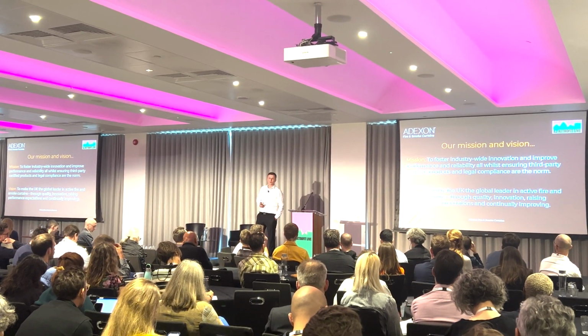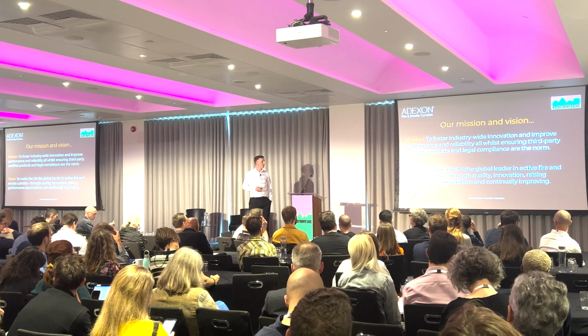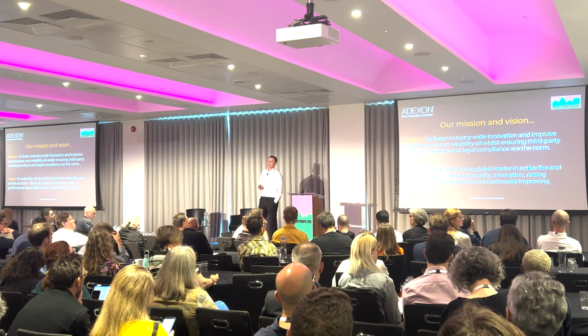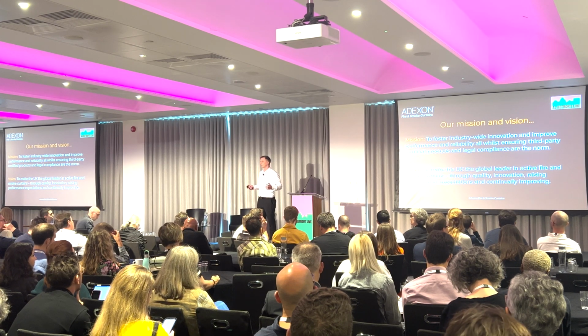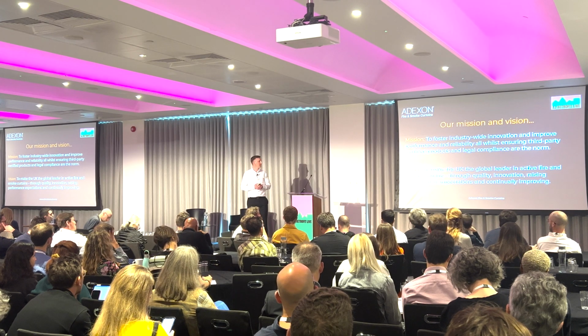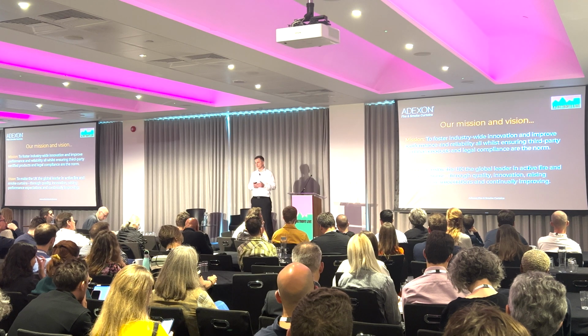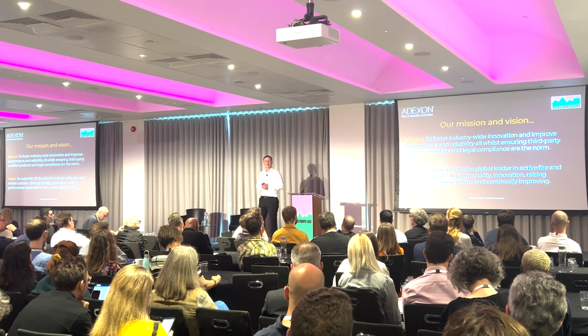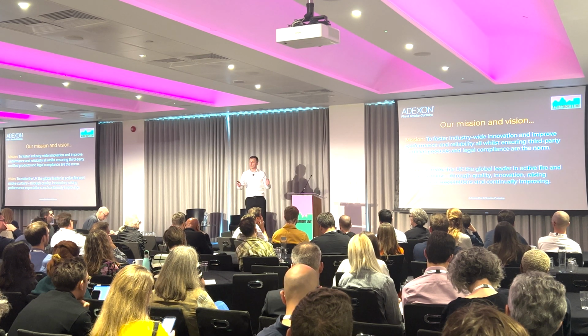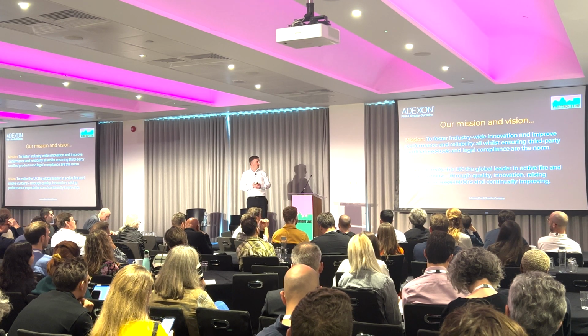If you want to conceal them in a ceiling void, they require less reinforcement and secondary steelwork for weight load bearing. And then there's also, we'll touch on this a little bit more, a lot more uses of them, because with fire curtains we can have horizontal designs as well as the standard verticals. We can achieve a lot more different classifications, E, EI and EW, and we can also do concertina, or some people know them as accordion, so there are no guide rails needed at all. We've got some of those going in at the new Liverpool Football Club at the moment.